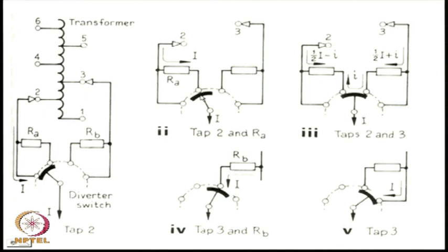Next, we move to the position where these two resistances are shorted by this diverter switch. This is the reason why these resistances are necessary, because without these resistances, if we move this diverter switch, then there will be a short circuit between these two taps and there will be large circulating current which may damage part of this winding. So, these current limiting resistances are necessary. Now half of the load current is flowing from here, half of the load current is flowing from here, and there is a circulating current small i.